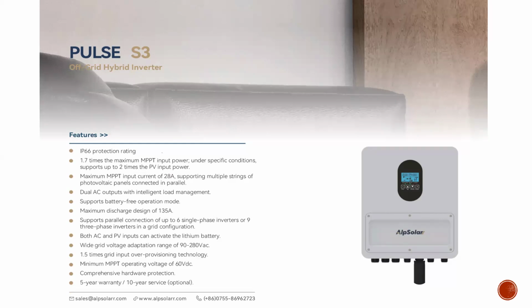So it has a maximum discharge design of 135 amps. This is another beautiful feature about this inverter. With a discharge design of 135 amps, it means this inverter can discharge 6 kilowatt power. At the same time, there are some inverters that cannot discharge 100% of the capacity. There might be a 6 kilowatt inverter, but it cannot discharge the full 6 kilowatt at the same time. But this inverter having a discharge design of 135 amps, we can do the calculation, depending on the voltage. Of course, this inverter is a 48 volt system. 135 times 48 is 6 kilowatt and above. So it means this inverter can discharge all of its capacity to your load to meet your load demand.